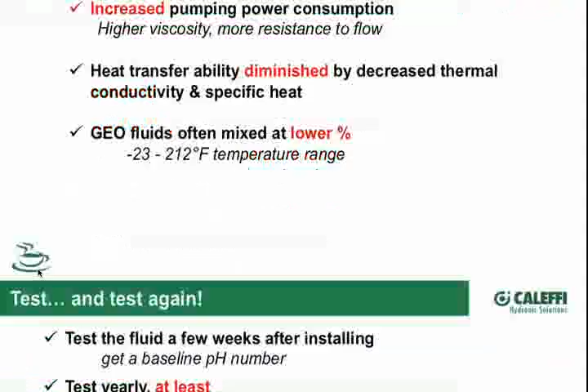This is what I use, and I think it's what you recommend in your operating guidelines and technical brochures: a little refractometer for testing freeze protection. You just open this little window, put a drop on it, there's a dropper on the side of the tool, close the window, and when you push it down a light comes on so you can read the scale really well. For the cost of that tool, I don't know why you wouldn't own one. It's a bit more accurate than the floating ball type and it's a durable product.